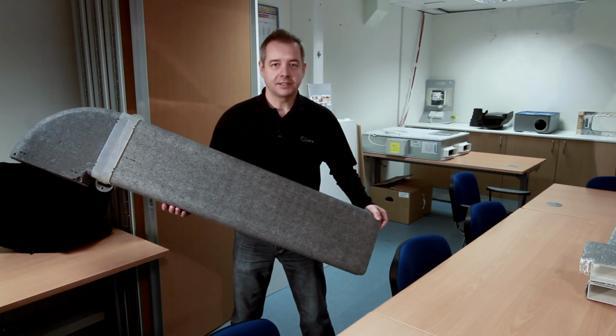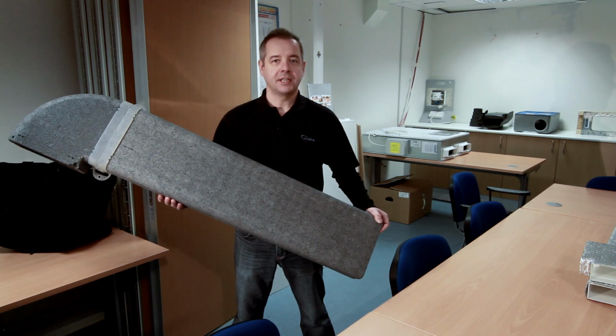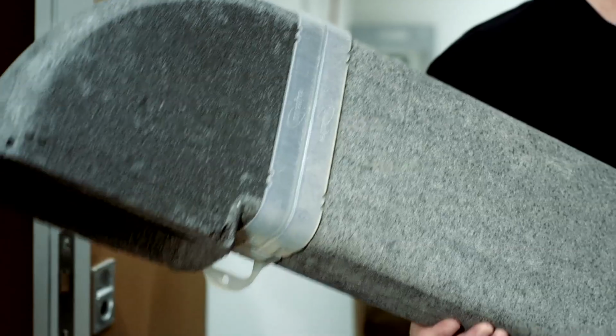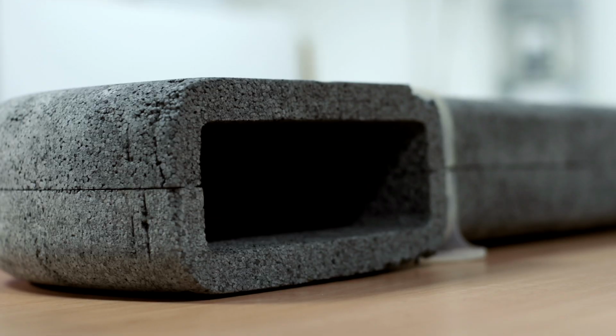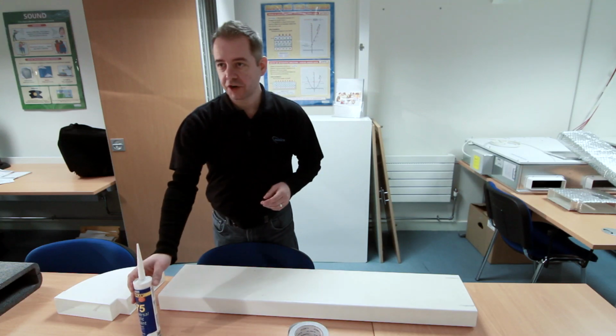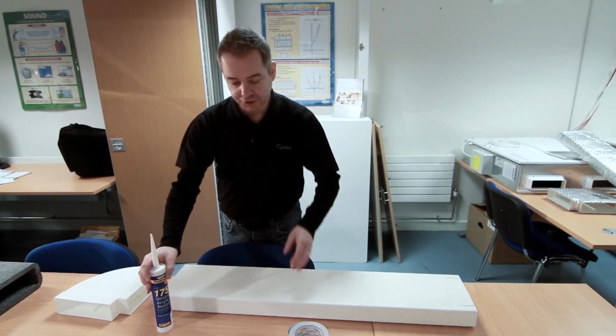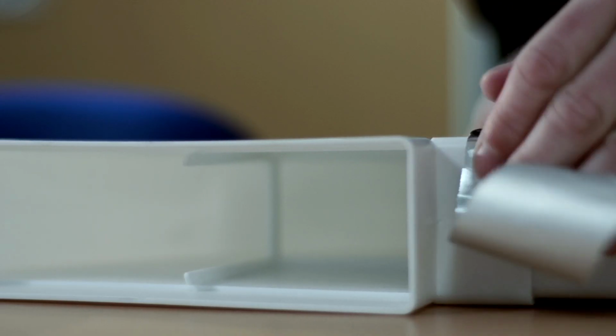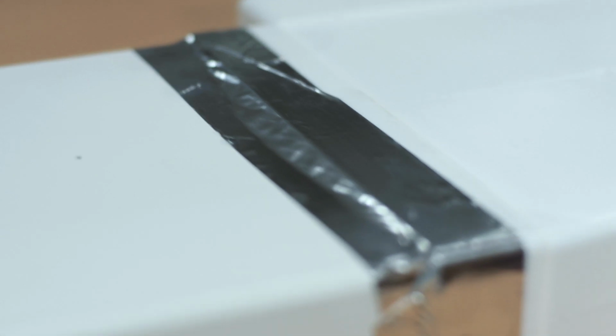When the need to insulate duct occurs, Nuaire recommends that the installation is carried out using its new thermal duct range. This ensures compliance with the current building regulations. Connections in ductwork should be made using a non-hardening acrylic duct sealant and a suitable tape. This is to prevent any air leakage which could affect the commissioning and the airflow of the system.